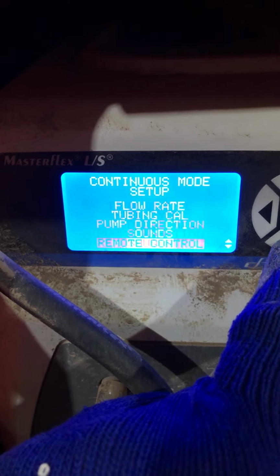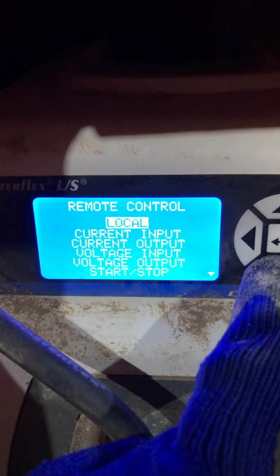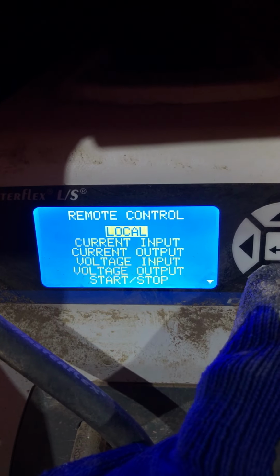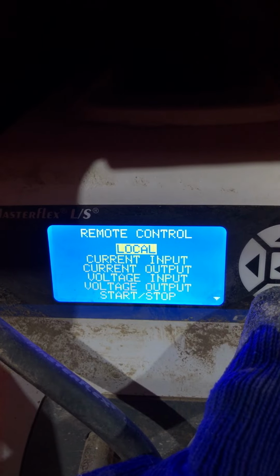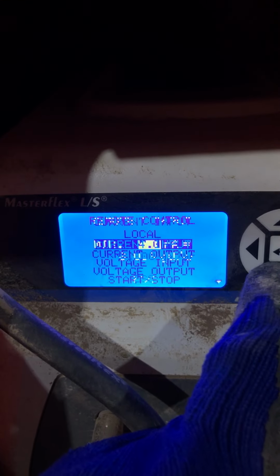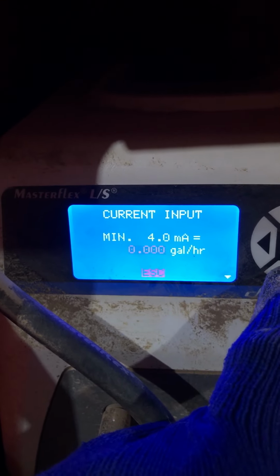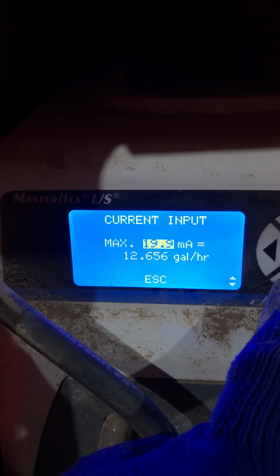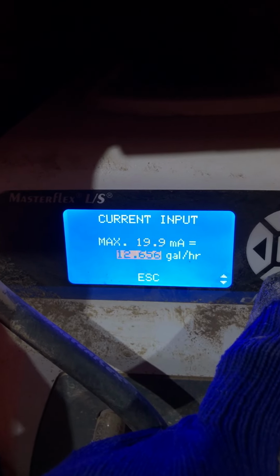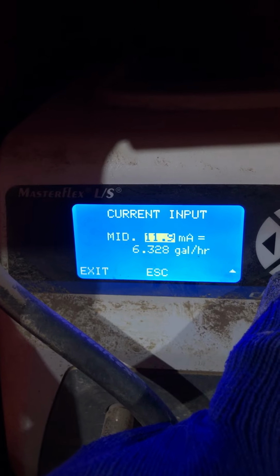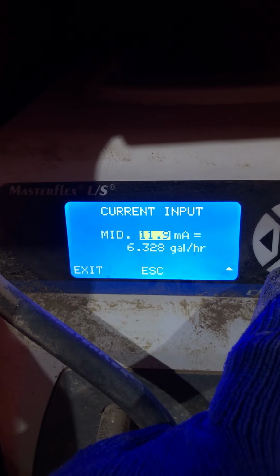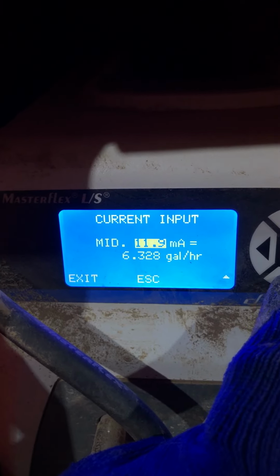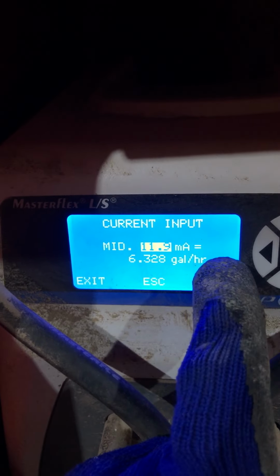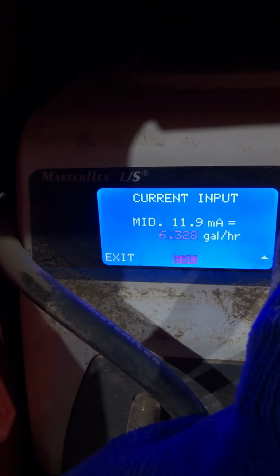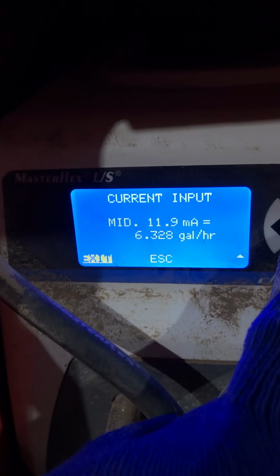Okay, now we go down here to remote control. So we're going to change it back to running on the Greentronics system. Current input 4.0. 19.9 is 12.65. We're good there. Now if we would have changed that 10 ounce number, it would have changed 12.65, and so we'd have to go in and just verify that these values are correct. Make sure to exit, not escape.